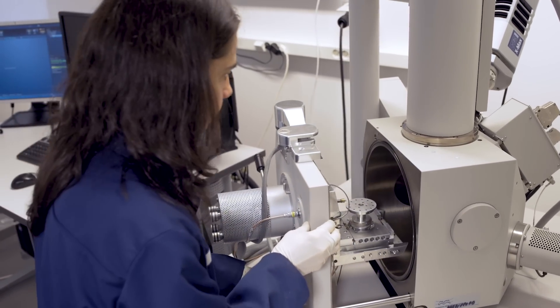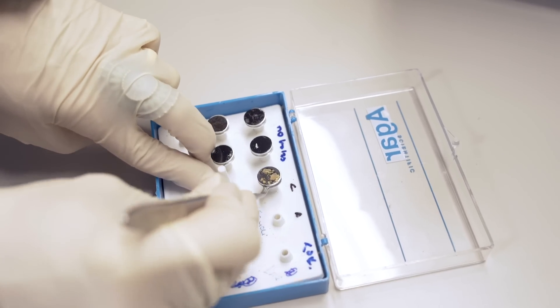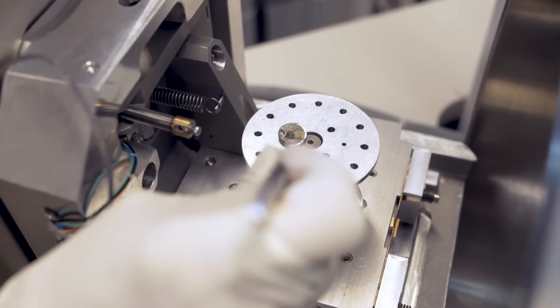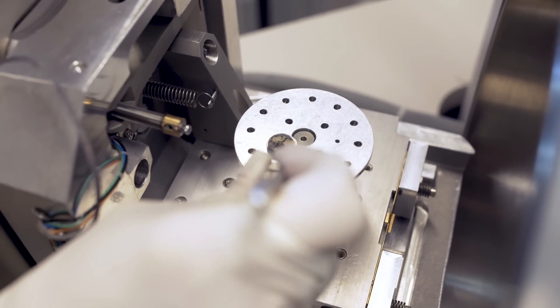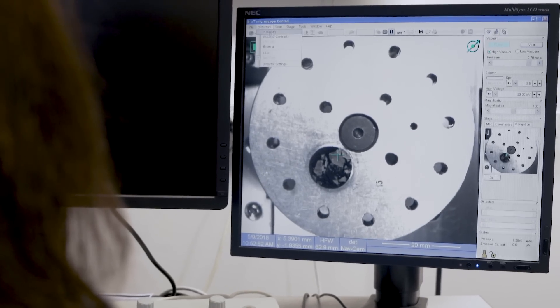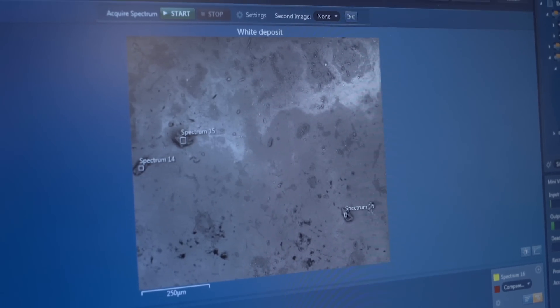When we get the fouling sample or a fouled plate from the customer, we need to know what the fouling consists of. We use our scanning electron microscope to see what is the elemental composition of the fouling. By knowing the elemental composition, the color of the fouling, and the application that the heat exchanger has been used in, we can determine the fouling type.